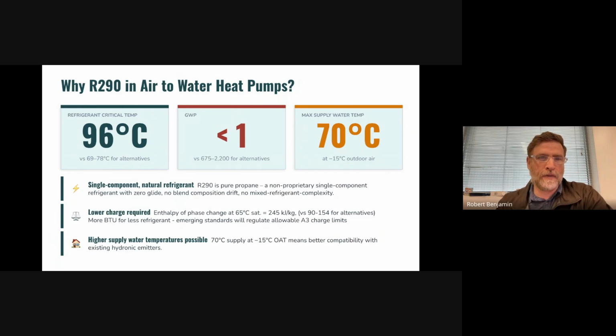Also, because of its ability to soak up energy, we can use less of the refrigerant, and especially in an air to water system, we're using it in a way that's less prone to leakage. One exciting aspect of this technology is that we can produce higher supply temperatures than a lot of other refrigerants, and it's still reversible, so we can still do cooling with the same equipment — as opposed to, say, CO2, which can also produce very high supply temperatures but has difficulty being incorporated into systems that are reversible or easily reversible.